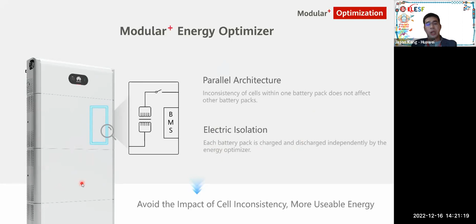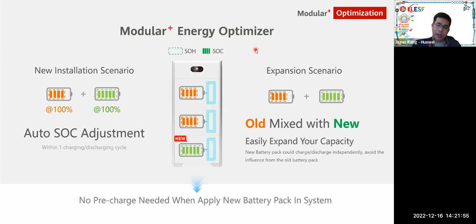Another point is SOC, or state of charge adjustment. With other technology, you have to adjust the state of charge when you couple with another battery, whereby the SOC of the other battery is different from this one. But for our solution, you don't have to adjust it, it will auto adjust because of the optimizer installed within the battery modules.